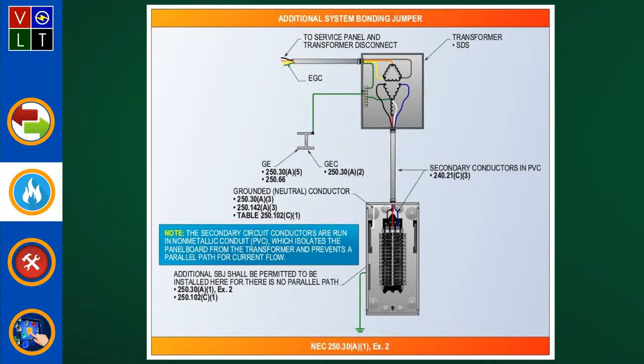I got you. Okay. Now, Exception 3 is going to get into your Class 1, 2, or 3 circuits. Basically, it tells you the system bonding jumper shall be sized not smaller than the derived ungrounded phase conductors, and it shall not be smaller than a number 14 copper or number 12 aluminum for any type of system that supplies a Class 1, 2, or 3 circuit and is derived from a transformer that is not rated more than what? 1,000 volt-amperes.